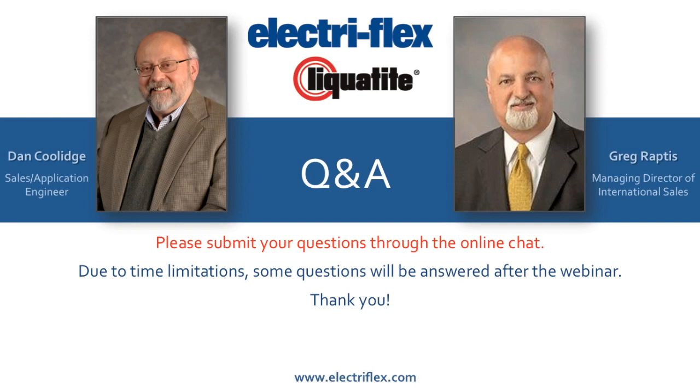Are there conduits available for temperatures above 150 C? 150 degrees C is the highest temperature rating for conduits we provide that incorporate a plastic material. We do also make non-jacketed all-metal flexible conduits, so there's virtually no temperature limit. The contained conductor insulation would be the only limiting factor.